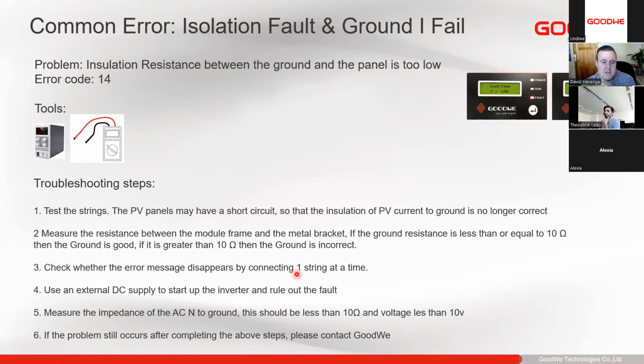If we get no results by doing one string by one, we can also use a DC power supply. If you start up an inverter with a DC power supply and it still gives an isolation error, then obviously the inverter is at fault. But if the inverter starts up and works fine, we can also measure the impedance of the AC neutral to ground, and this should be less than 10 ohms, and the voltage, if you measure the voltage, less than 10 volts, sorry. If the problem still persists, create a support ticket and provide all the information of your fault finding so that we can replace the device for you.